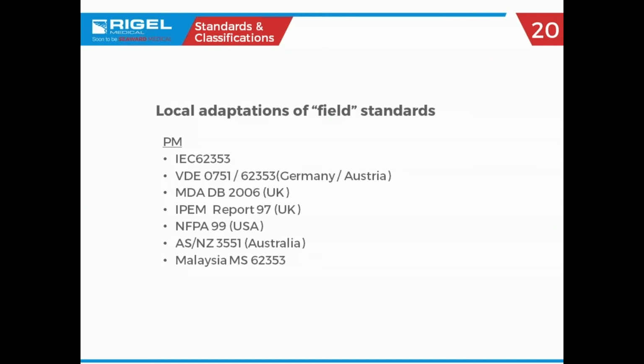They do ground continuity or ground bond testing, if you're more familiar with that, at 25 amps. If you do that long enough, continuously enough, that piece of medical equipment, you're going to have dielectric breakdown of your insulation. So if you keep high potting something at 1,500 volts continuously, it will fail. So the field standards are a little softer, easier, kinder to the medical device. So we don't do high pot testing at 1,450 volts, whatever it is. We don't do ground bond testing at 25 amps. We do it at 200 milliamps.